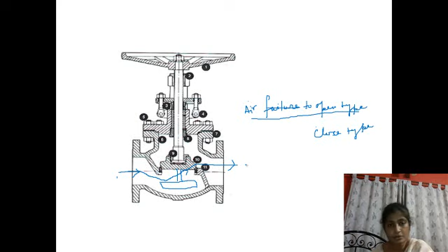So depending on the type of control action, rather on-off control action, that is the maximum energy input or minimum energy input, for two different types of valves, the energy flow to the process will be just of reverse type. For one type, the energy flow is maximum. For the other type, the energy flow is minimum. So on-off control action is dependent on valve type also.